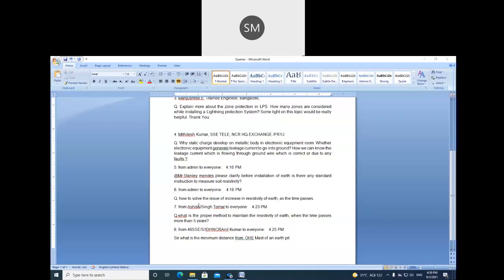Please clarify, before installation of earth, is there any standard instruction to measure soil resistivity? What we use is mostly the four-point Wenner method to measure the soil resistivity. So this is what you can use. How to solve the issue of increase in resistivity as time passes? Now, the resistivity depends on the moisture and the temperature. But after a certain temperature and moisture content, it stabilizes. So this is what the standard says. But it will change. It cannot be stable all the time. As the water content in the soil reduces and the temperature increases, the resistivity increases.